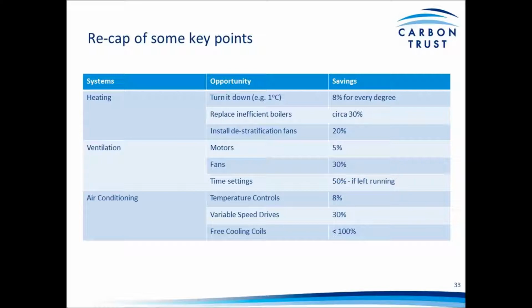Ventilation: high efficiency motors can save 5%. Effective control of the fans via airflow modulation, or through upgrading to higher efficiency electrically commutated EC fans, can save 30%. Timer settings: if they're running out of hours, running overnight, you can cut their energy consumption by half very quickly. Air conditioning, as with heating: effective temperature control, variable speed drives on your compressors within the refrigeration system to modulate external condensing temperatures, and investing in free cooling units if you are undertaking major plant upgrades.